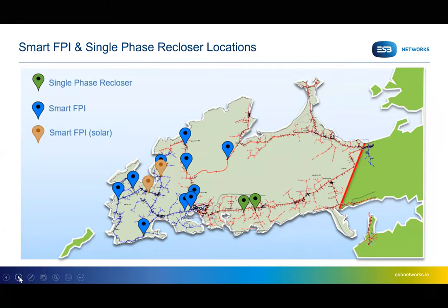Fault passage indicators are new in ESB Networks. We've had a number of trials, and there are other trials ongoing in other parts of the country, but the smart FPIs we're trialing in Dingle are allowing us to see whether the data from these devices can be used to better pinpoint where faults have occurred on the network, enabling us to send repair crews to a more specific location. Traditionally they would have been required to patrol a long section of line to find a fault, so there's a lot of safety value as well.